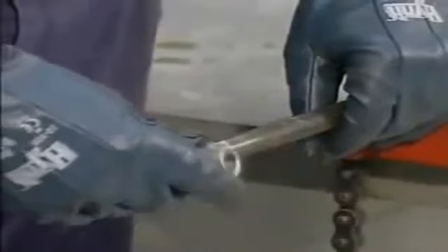Threaded joints, or screwed joints, are made by screwing the outside threaded end of a pipe into the inside threaded end of a pipe fitting. Threaded joints have a specified engagement depth. The engagement depth is the distance that the pipe must be turned into the fitting. The engagement depth requirement must be reached for the joint to be properly threaded.